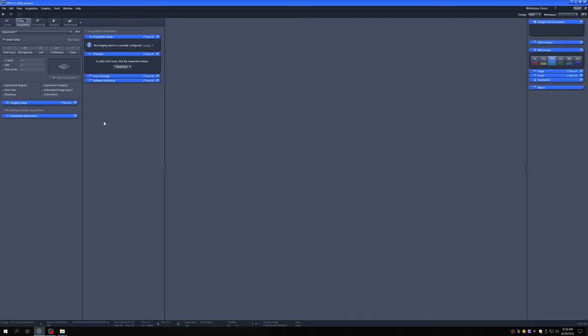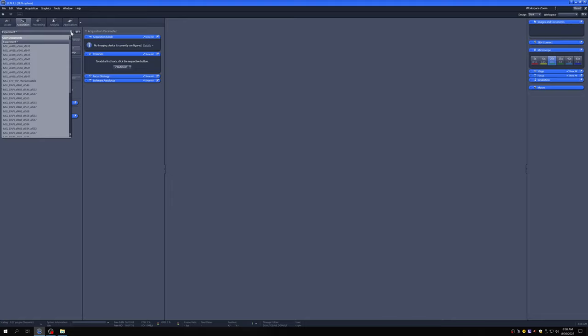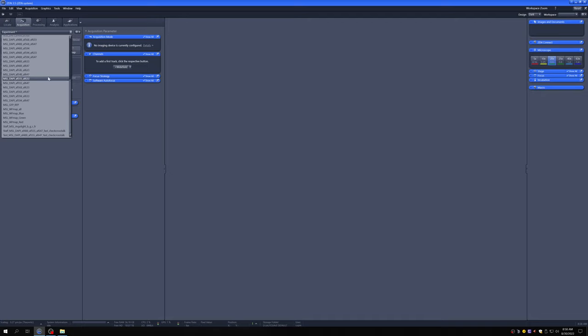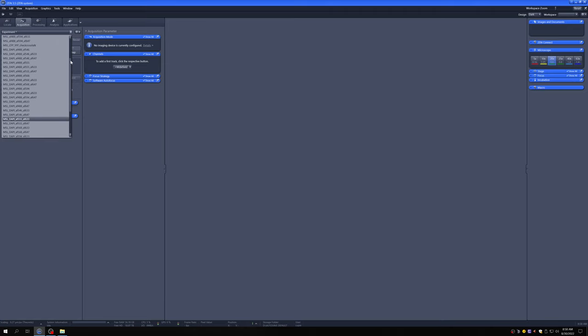So to load completely new settings, which is what you do when it's the first time you've done something or the first time you're going to do things in a certain way, you go to this drop-down menu, you click here, and then you scroll through and find a setting that starts with MSL and that then has three or four fluorophores that are very close to or include the ones that you are interested in. If you have fluorophores that are not very conventional and that are not on this list, let me know and we can make a special setting for you.